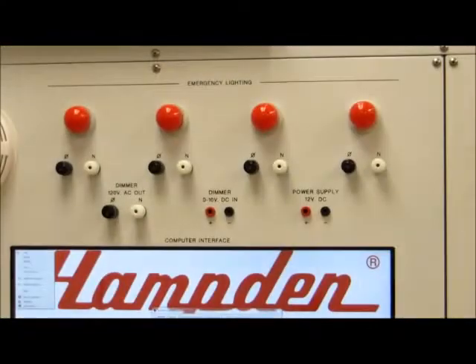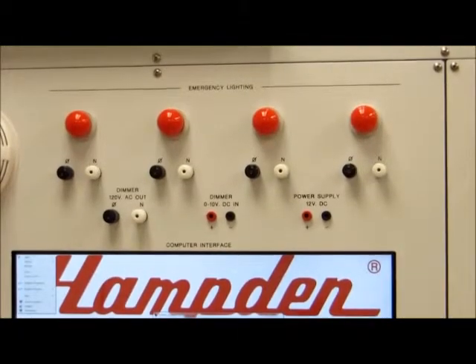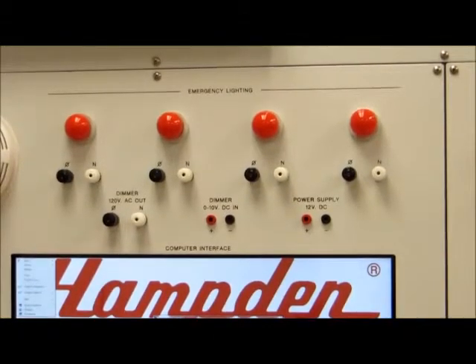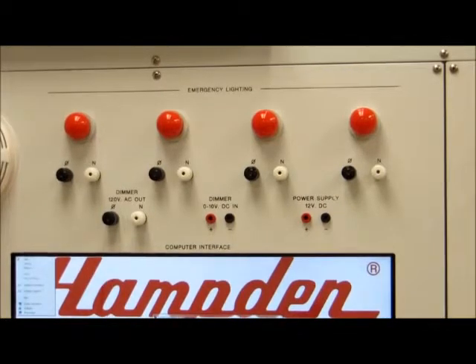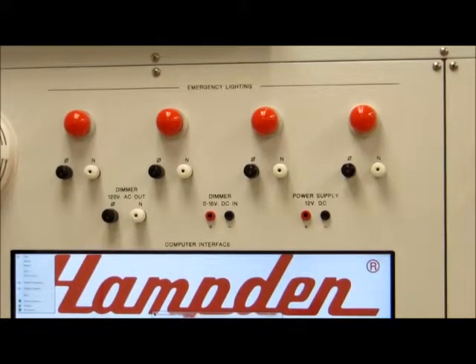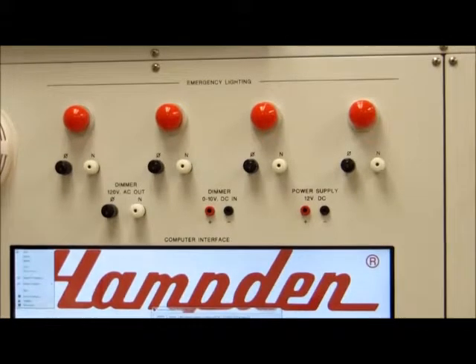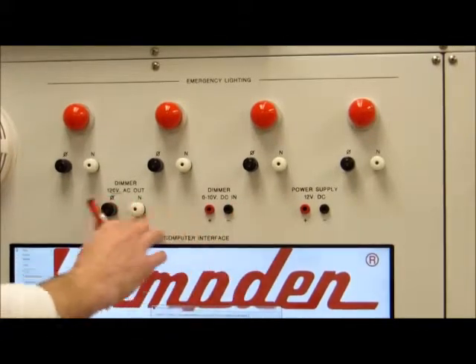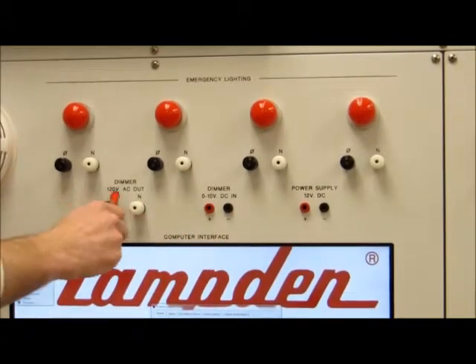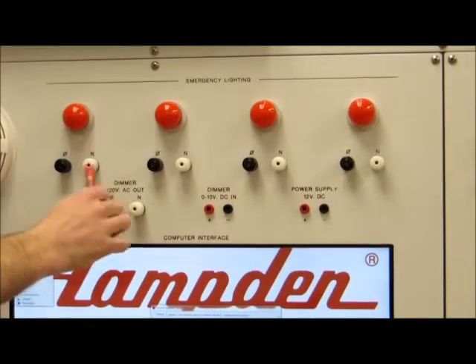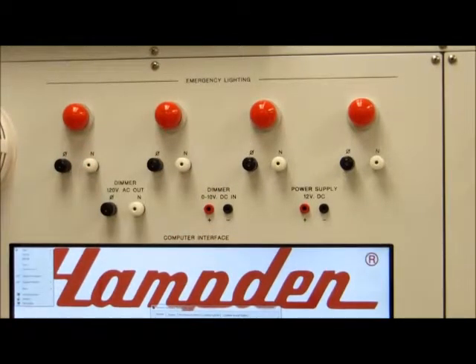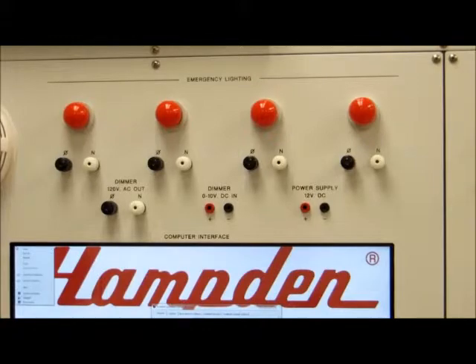This is the emergency lighting section. These lights do not talk over the network. They are powered through an output from our I/O modules. A 0 to 10 volt signal comes in to the dimmers, which then outputs a 0 to 120 volt AC signal to the lights, which vary the brightness of the lights.